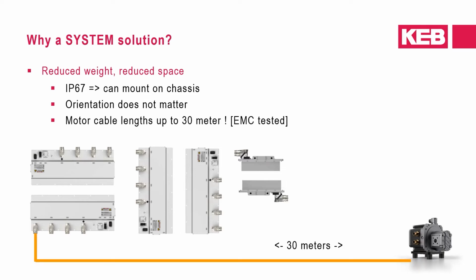The T6 also supports motor connections up to 30 meters. A common concern in regards to the distance between inverter and auxiliary motor is electromagnetic interference, but this was taken into consideration during design of the T6 system. Attention was given to the clamping and shielding of connectors to allow for the longer cable lengths. Additionally, each inverter stage has an integrated DC choke to protect against EMI.